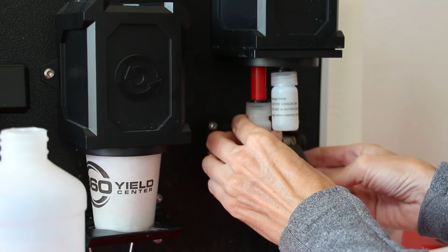And you do want to make sure the lid is secure on that, otherwise you'll get air in there and your standard solution will evaporate throughout the season. And if your standard solution evaporates and leaves it in a dry environment, then you're going to have a bad reference electrode starting out the season next year. So just make sure that that is screwed on tightly and securely so that you're not having to worry about any evaporation taking place on that end of it.